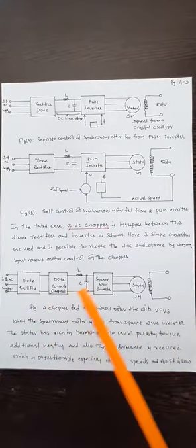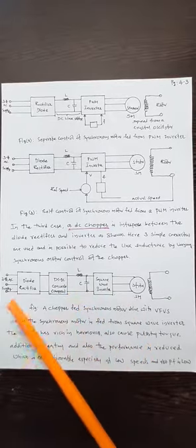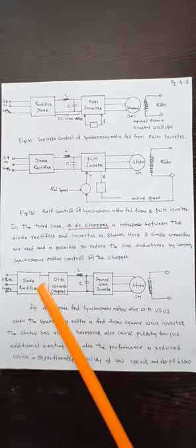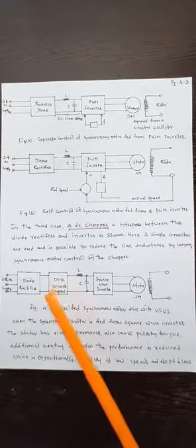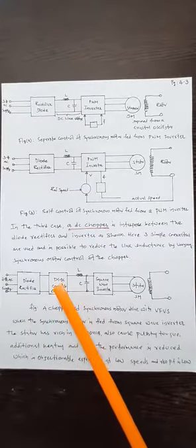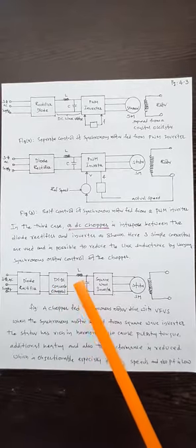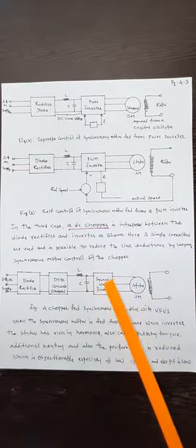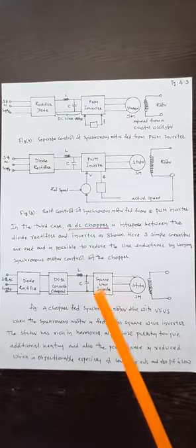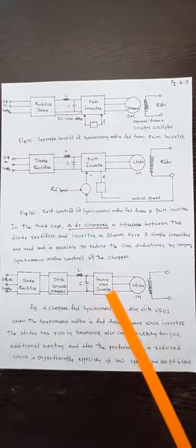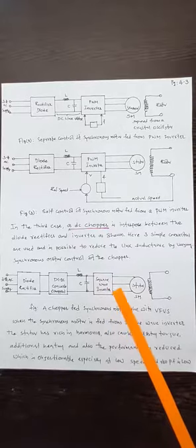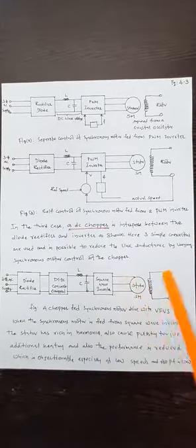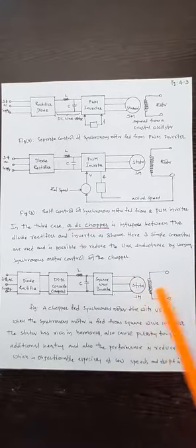Here there are three stages of conversion. Three-phase AC supply is fed to a diode rectifier, which converts AC into DC. This DC is given to the chopper. The chopper converts fixed DC into variable DC, which then passes through the filter for purification and is supplied to the square wave inverter. The square wave inverter provides variable voltage and variable frequency, which is fed to the synchronous motor.